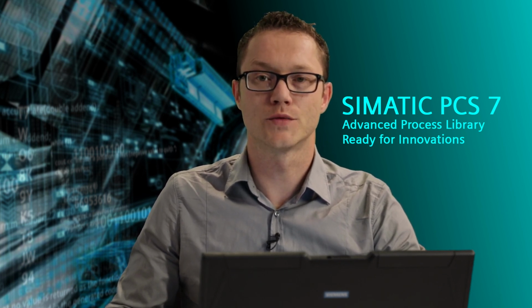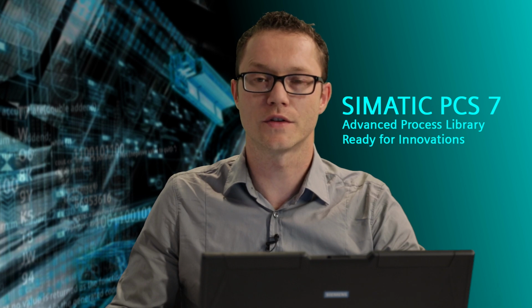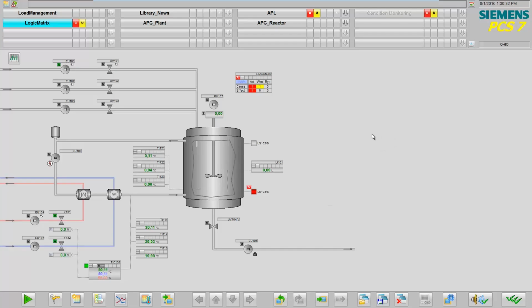The PCS7 Logic Matrix is a tool for creating and visualizing interlock logics based on the principle of a cause and effect matrix. Here you see a typical process plant containing a reactor. This reactor is filled by means of a wide variety of pumps and valves and is also drained through these pumps and valves. The combination of pump and valve generally requires an interlock so that a pump, for example, will not initiate a pumping action against a closed valve. These interlock logics are implemented by the PCS7 logic matrix.